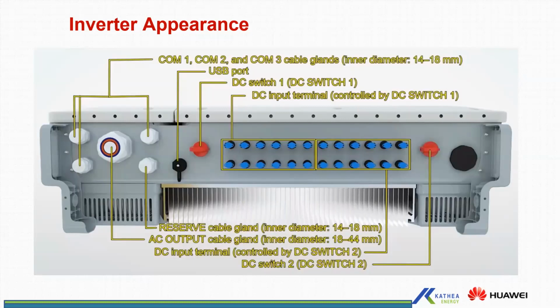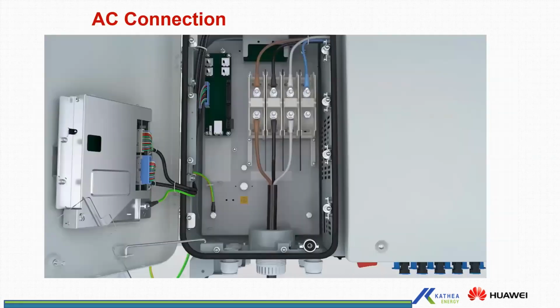And then the inverter has a USB port with a cap. So after doing a local commissioning, if you are not using the port, preferably just close it. The inverter is IP65, so it can be installed outdoors. To make sure that all your IP features are maintained, you just need to secure the USB port with the lead which is supplied with the inverter. So this is how the maintenance compartment looks.